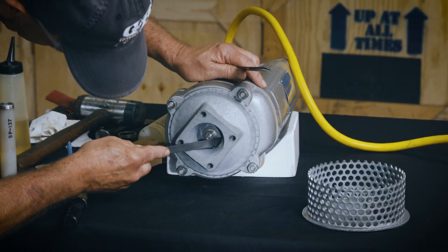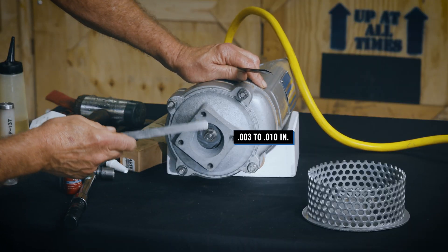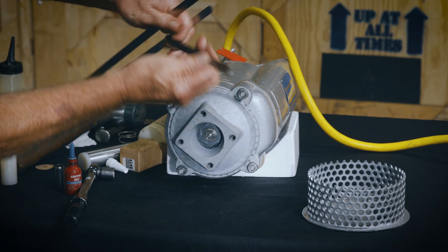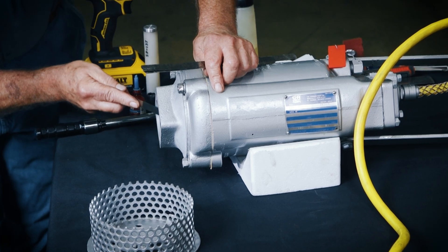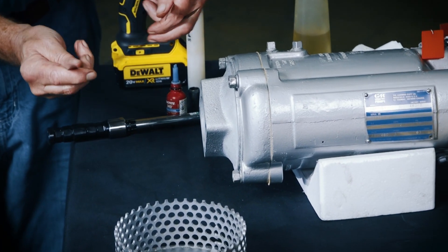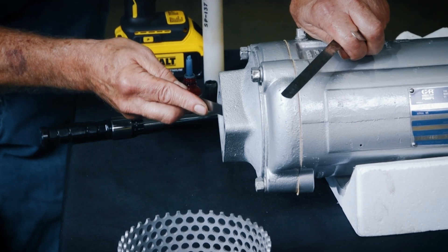There should be a clearance of 3 thousandths to 10 thousandths of an inch between the suction casing and the face of the impeller. Reach into the suction casing with a feeler gauge to measure this clearance.